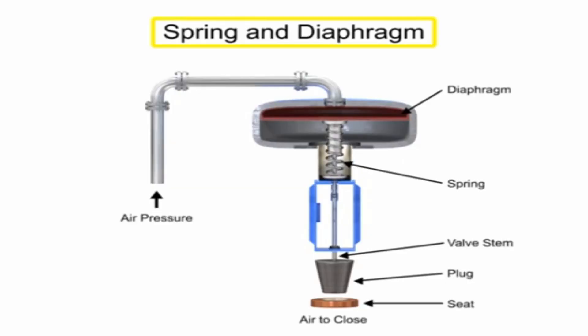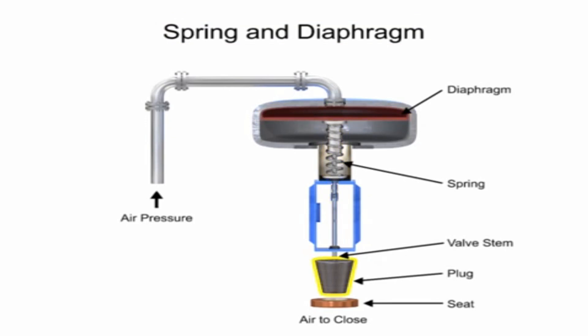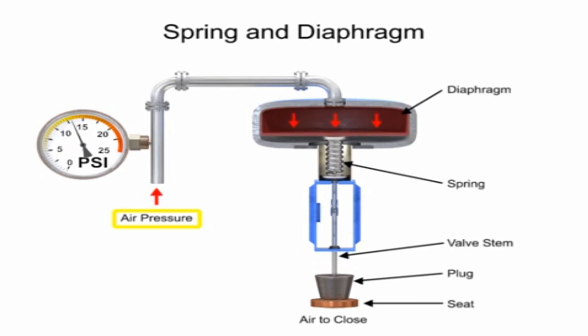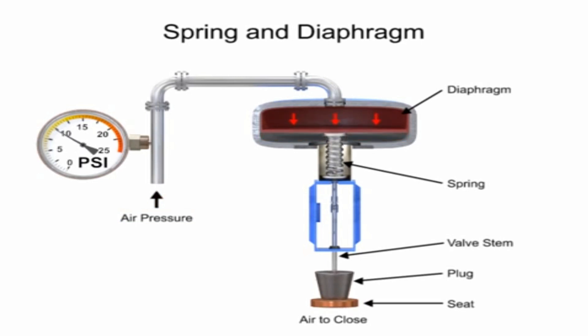So first and foremost, what is basically an actuator? This is a control valve actuator — a diaphragm type actuator. You could see over here: the air enters into the tubing, gets into the actuator, and pushes against the opposing spring tension, which in turn pushes down the stem. This is how it operates a control valve and throttles it during operations — either giving a tight shutoff, full open, or throttling.